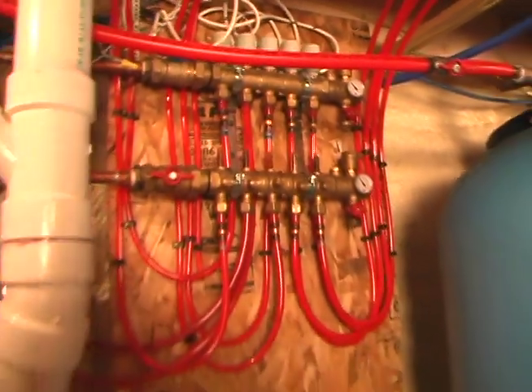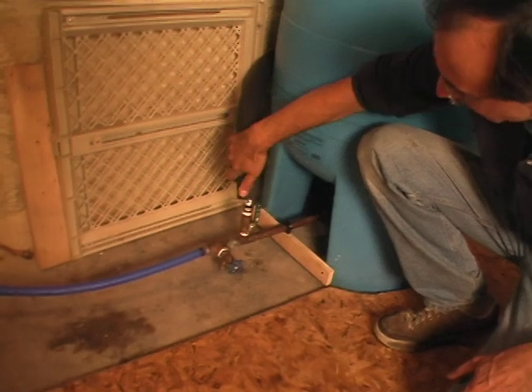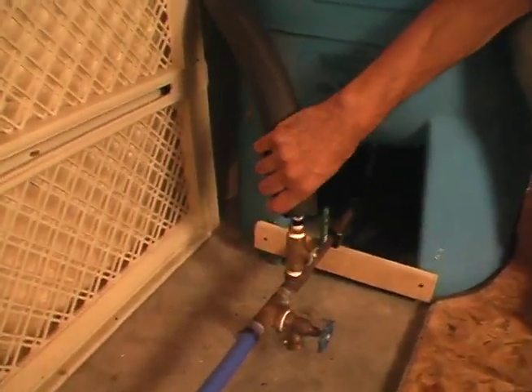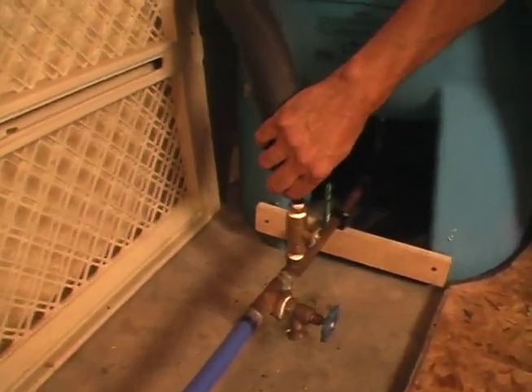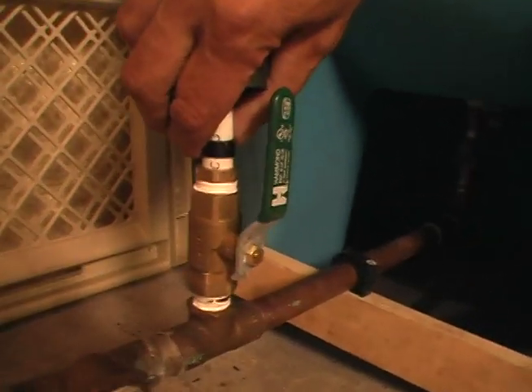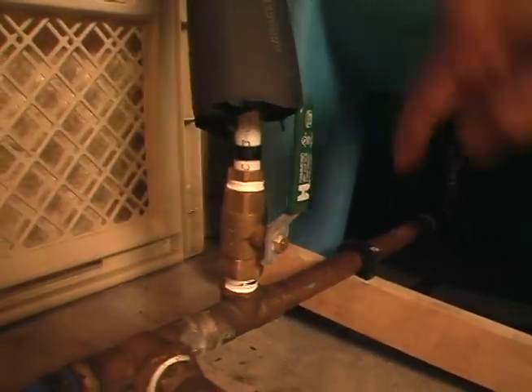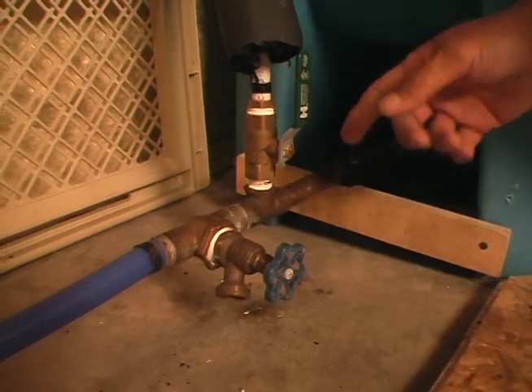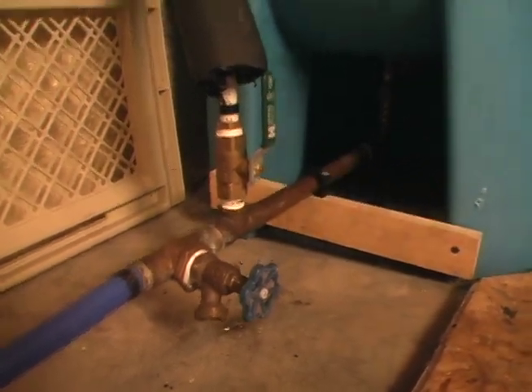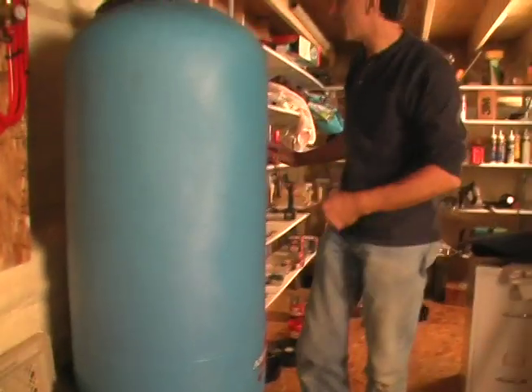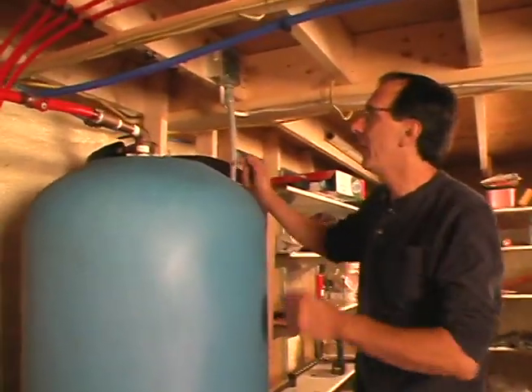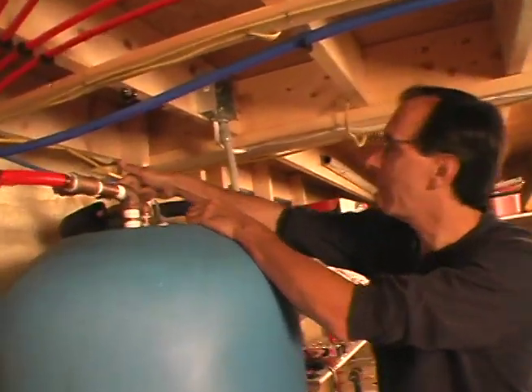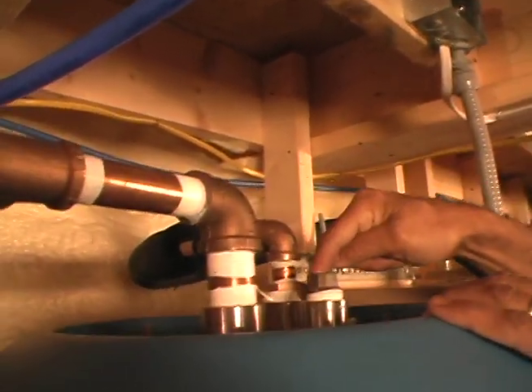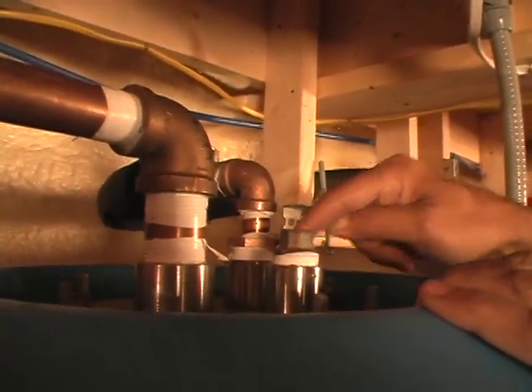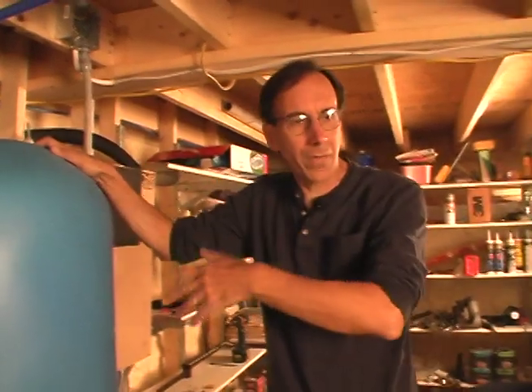The other tie-in we have is a line over here. This white line is the cold water drawing off the bottom of the tank, let me get this right, and that goes to the heat pump. The heat pump has its own circulator pump. Then hot water discharges in this line here into the top of the tank. And that part of it is fairly simple.